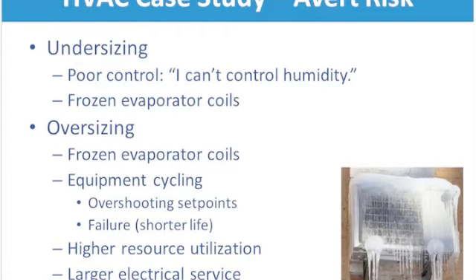But the flip side of that is oversizing. When you oversize, a bunch of other problems can happen, including poor control. A lot of times you'll actually get frozen evaporator coils in the room because it's trying to draw out heat when there isn't any, since it already pulled it all out due to being so oversized. But you're still asking it to stay on because you still want humidity control.